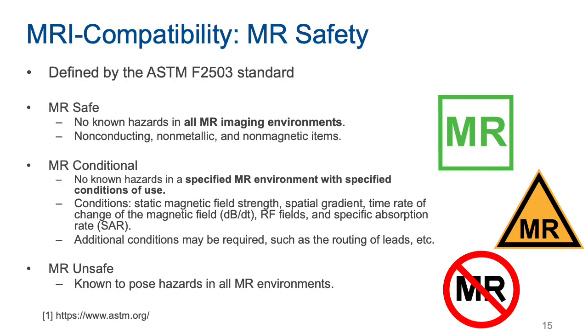I think many of us are already familiar with this, but there is a standard that defines the 3 classes of MR safety. The first one is MR safe, meaning that the device does not have any known hazards in all MR imaging environments. This includes non-conducting, non-metallic, and non-magnetic items. The second one is MR conditional. An MR conditional device does not have known hazards in a specific MRI environment with specified conditions of use. These conditions are defined by the field strengths, spatial gradients, slew rate, RF fields, and specific absorption rate. You may have additional conditions such as how the cables are routed and connected. The third one is MR unsafe. MR unsafe devices have known hazards in all MR environments and should never be brought into the MRI room.